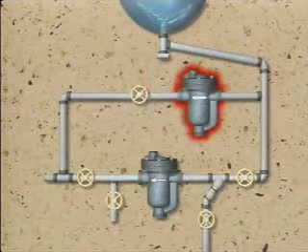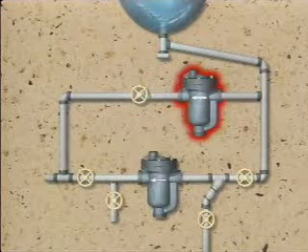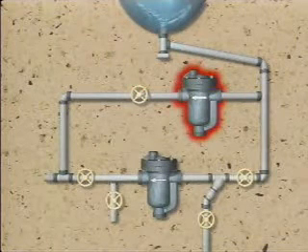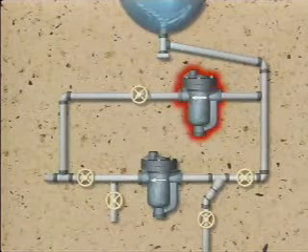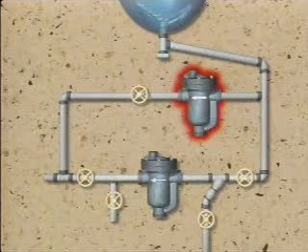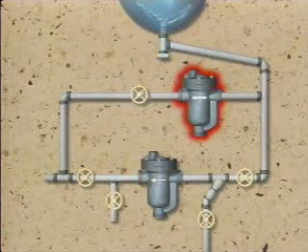Sometimes a steam trap is installed in the bypass line. Then if the main trap fails, the bypass trap can be put into service and the problem of blowing steam through the bypass line is eliminated.